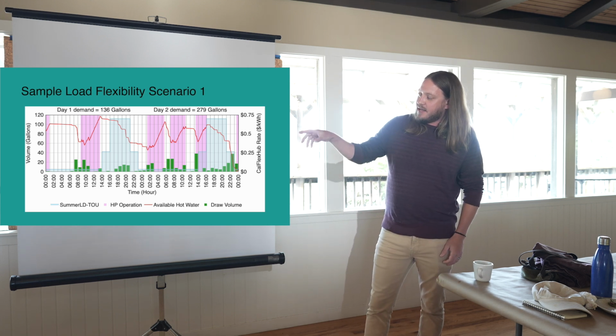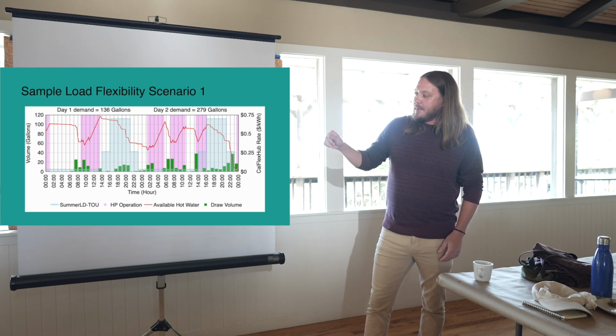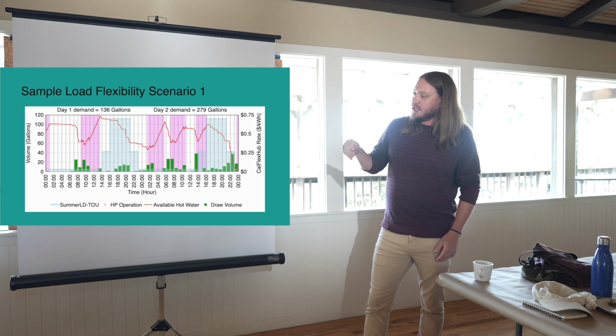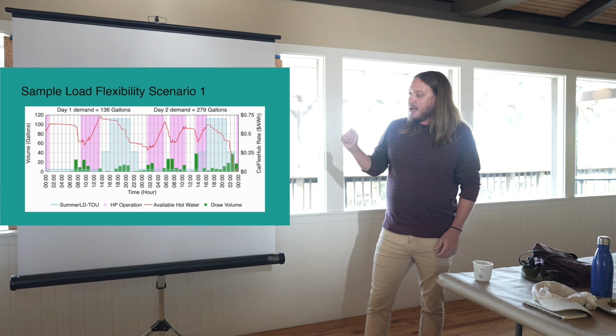We were able to maintain that storage until beyond peak. We still have about 40, 50 gallons of peak at midnight there. And now we're able to recharge again on the second day to get us back up to a full charge. Day number 2 had 279 gallons of hot water demand, so almost double.